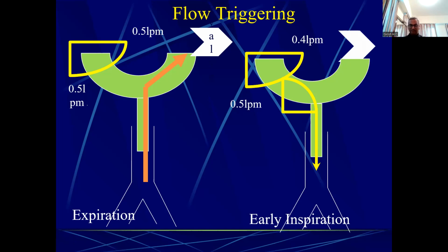Am I clear about the flow triggering? So where will be the sensors of this? In the proximal. Okay, this is inside the machine. This circuit is inside the machine, in the inspiratory limb. So this is constantly flowing like this in a closed circuit. Once there is a little bit draw from there, it senses this draw. And once the exhalation valve closes, the major flow, whatever 40, 50 liters, and whatever pressure you have set or volume you have set goes into the patient. So this is the bias flow, not the main flow.